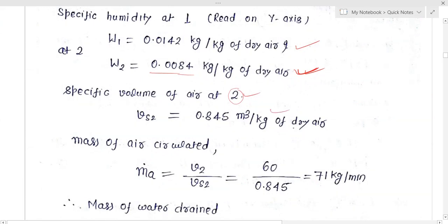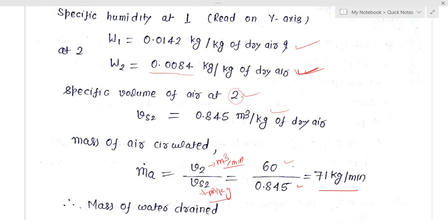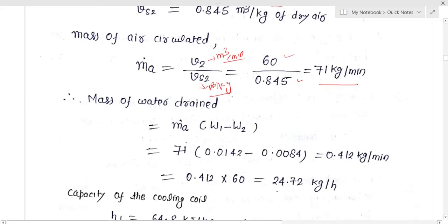The specific volume at point 2 is read from the psychrometric chart as 0.845 cubic meters per kg of air. To calculate the mass of air circulated, divide the volume flow rate by the specific volume: 60 divided by 0.845 gives 71 kg per minute — meaning you require 71 kg per minute of air to be circulated in the conditioned room.